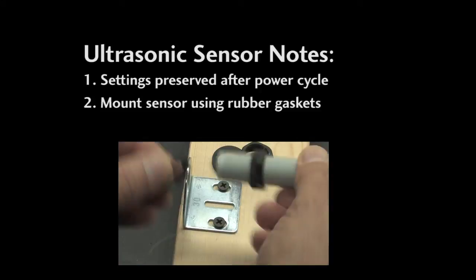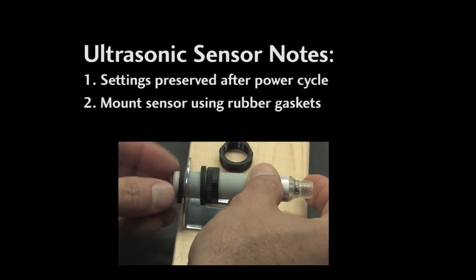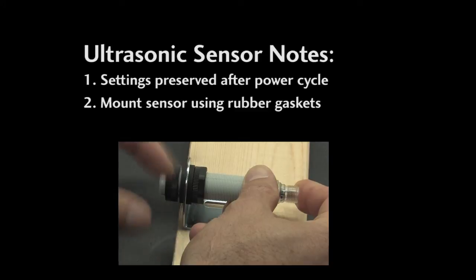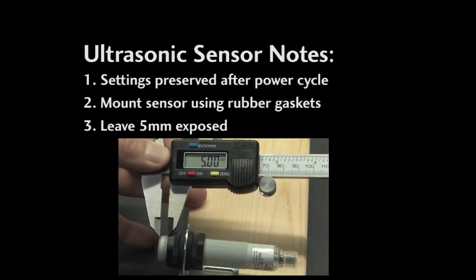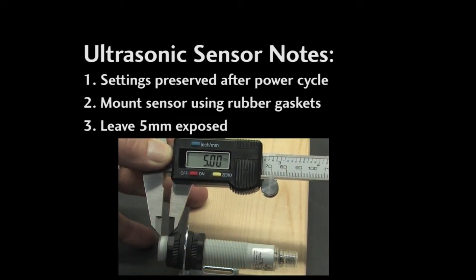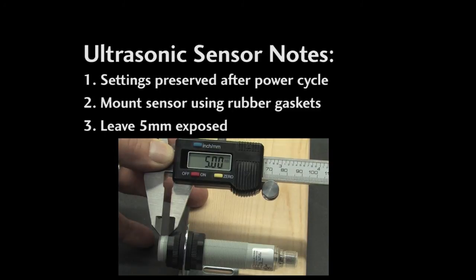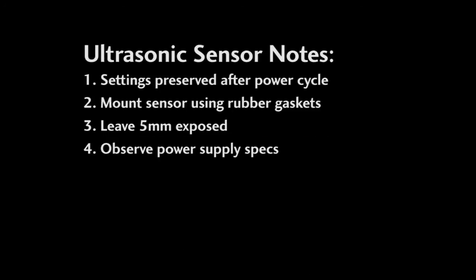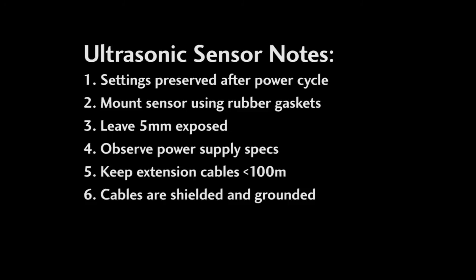A few notes – these settings are preserved even if the sensor is powered down. Make sure you mount the sensor with the provided rubber gaskets – they help provide vibration isolation. Also, make sure you leave about 5 millimeters of the housing exposed below the face of the sensor – so don't mount the sensor flush to the panel. Make sure the power supply meets the specs in the datasheet, the cable extensions are kept below 100 meters, and that the cables are shielded and grounded to help prevent electrical noise issues.